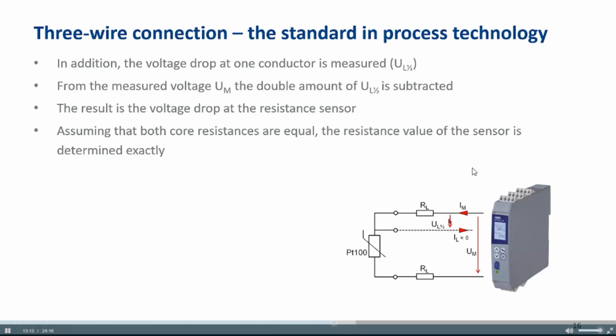On the other hand, we measure this voltage, which is the voltage drop on one wire, on one core. And then the device works in this way. The device says, okay, let's take this whole voltage and reduce it by 2 times the voltage which dropped on one core, on one cable, on one wire. And then theoretically, the transmitter finds out the resistance which we have on the Pt100.